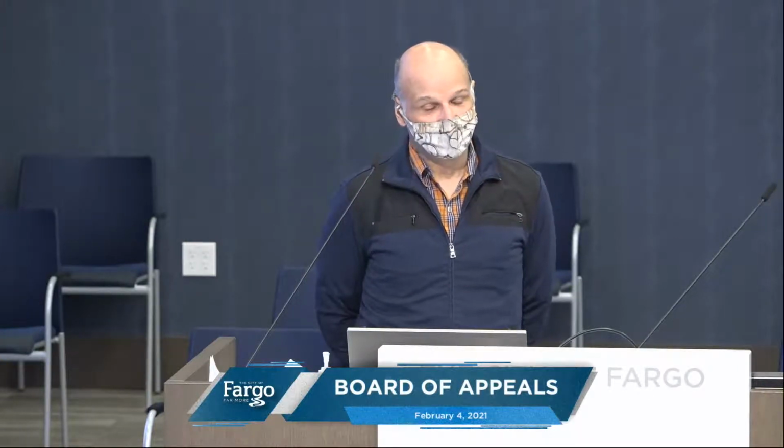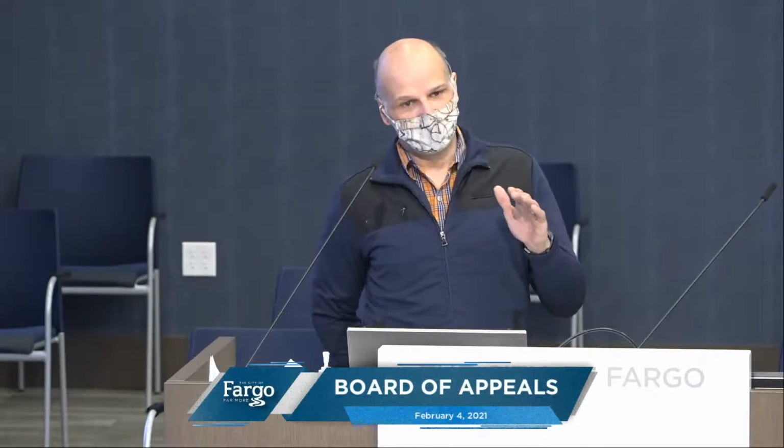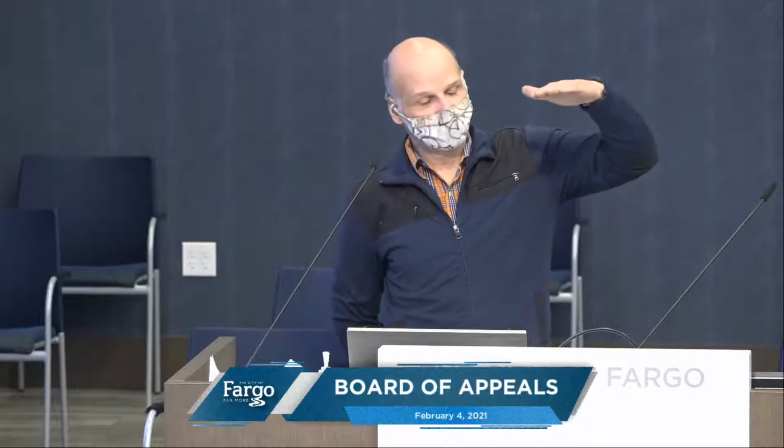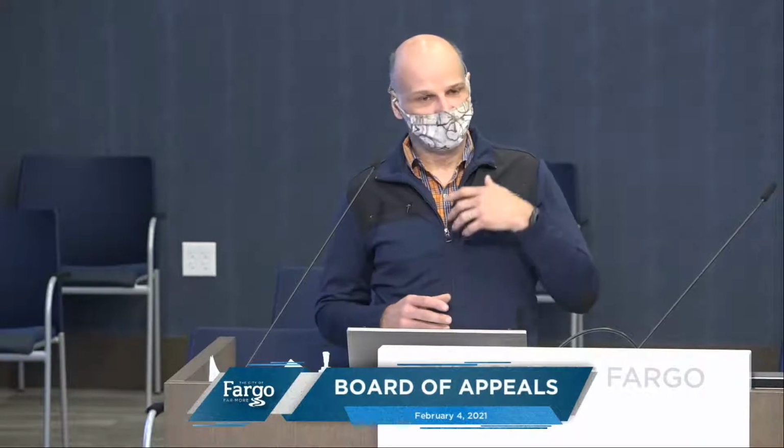But the designer of the sprinkler system for the condominium units expressed to us that to provide sprinkler separation within the double T type construction is very difficult. The floor of the garage is nice and smooth, but the bottom has these 30-inch projections that hang down, and any sort of a sprinkler system would require significant ancillary equipment.